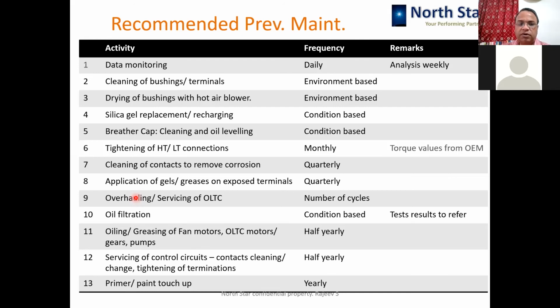Okay, cleaning of contacts to remove corrosion and erosion. You can apply gels and greases on the exposed terminals so that they won't get corroded because of moist and humid air. Overhauling and servicing of OLTC based on the number of cycles.